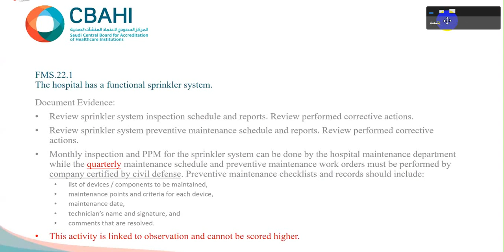Please bear in mind that PPM, especially the quarterly PPM for the sprinkler system, fire alarm, clean agent, wet chemical, and fire hose standby, should be done by a company certified by civil defense, especially the quarterly PPM for all these systems. This is just a photo from one of the hospitals. You can see that the sprinkler deflector is very close to the cabinet of medical record. As per Saudi building code and NFPA, it should be between 45 to 50 centimeters.